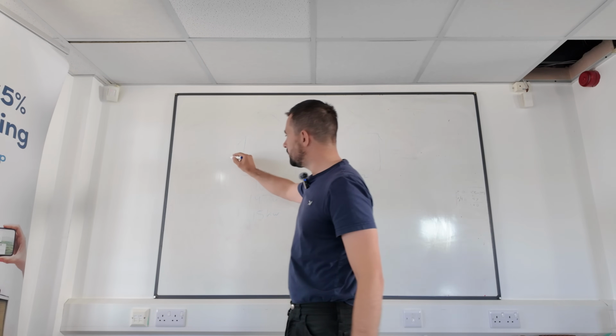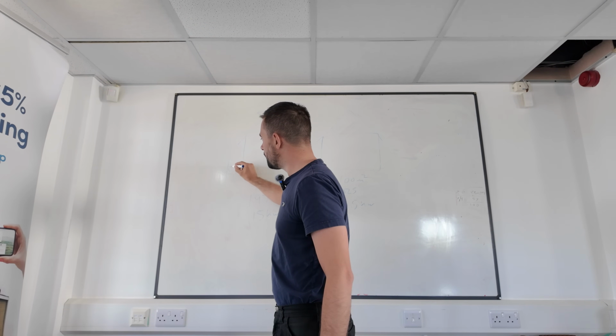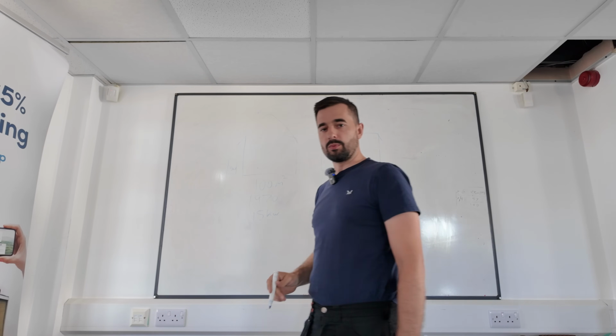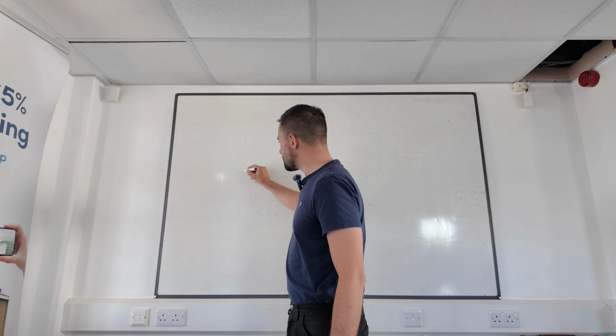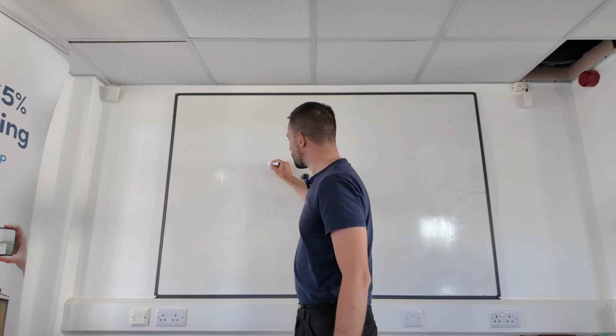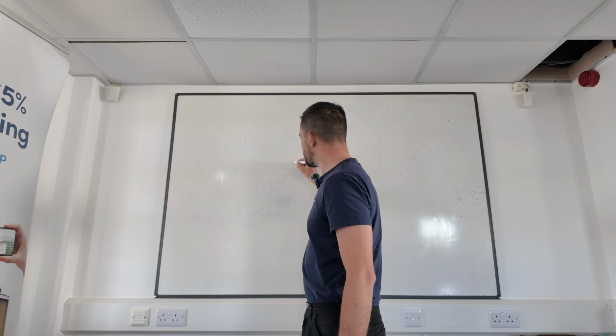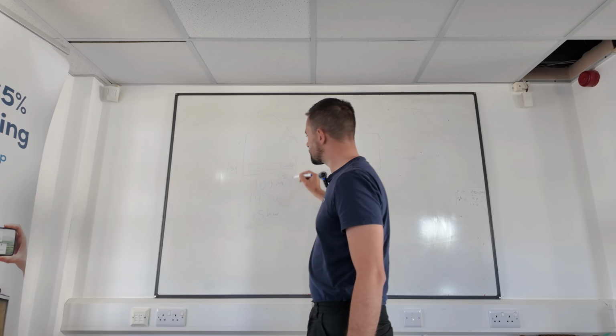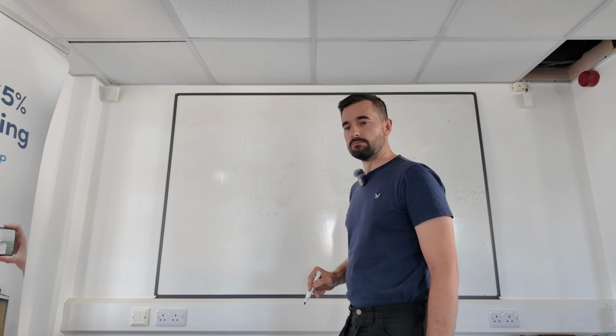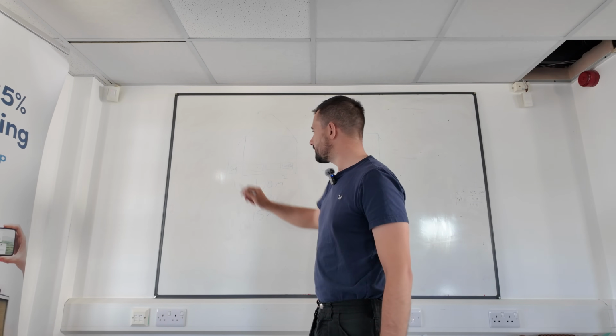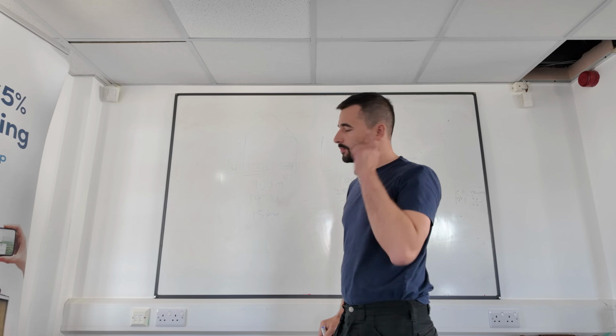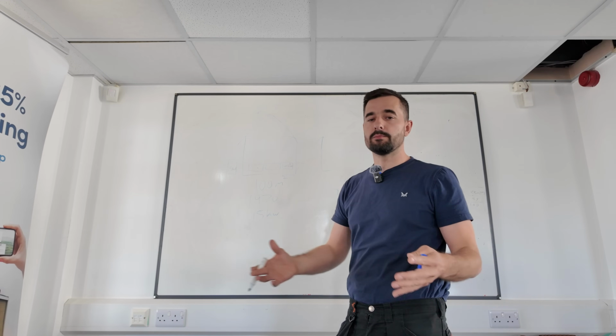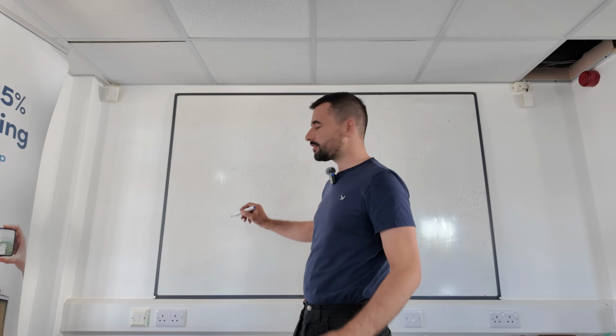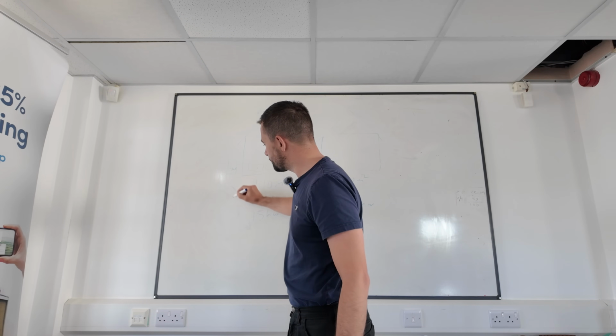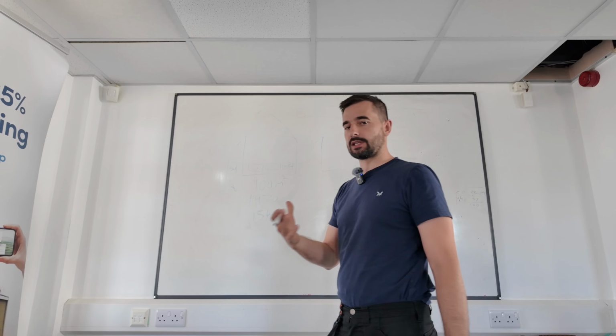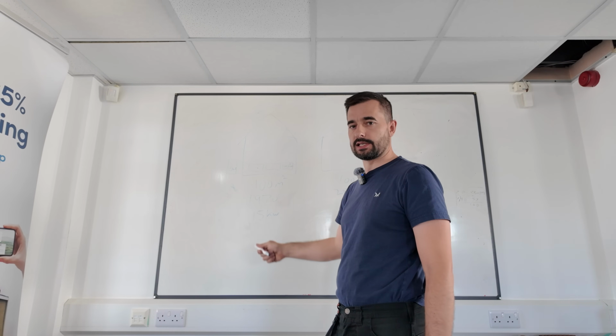If I install a heat pump that has a 15 kilowatt output on it with radiators, they're obviously going to be quite large, designed at 45 degrees Celsius, that house will get warm. 15 kilowatt heat loss, 15 kilowatts going in at a design temperature of 45. With most modern heat pumps, you will be getting a seasonal efficiency of 3.8, okay, 380% efficient, 1970s house.